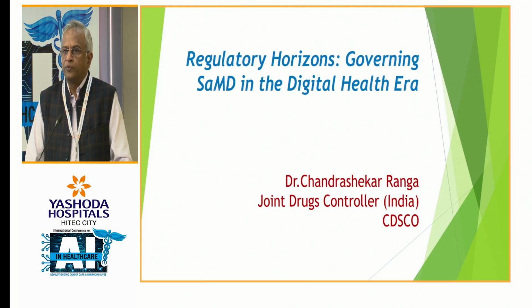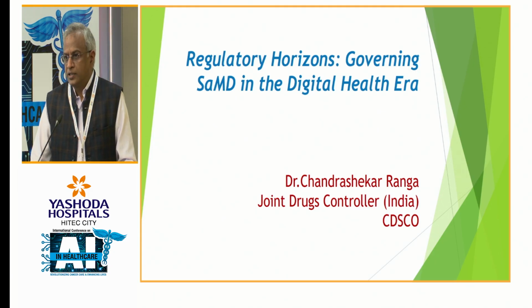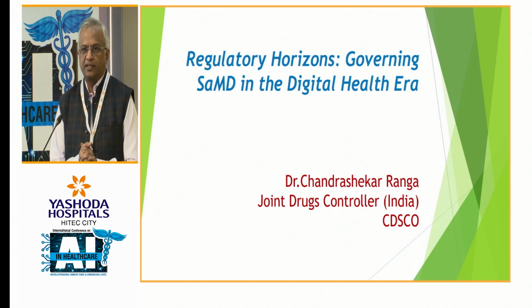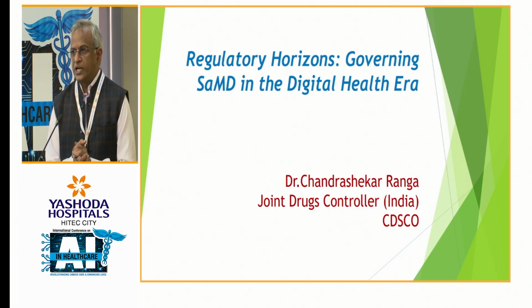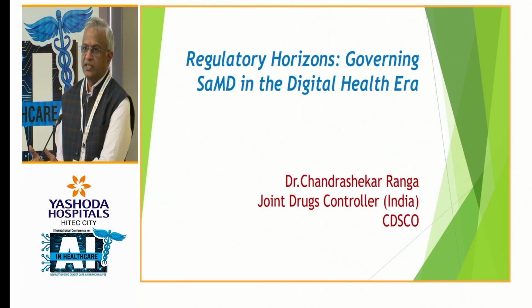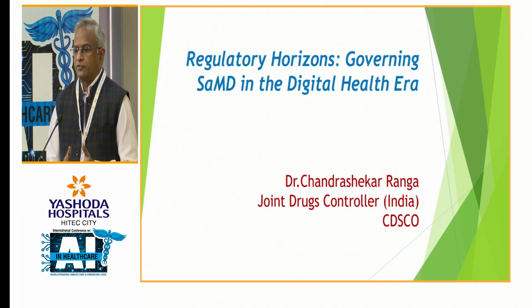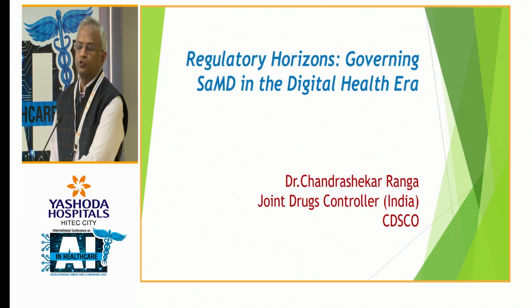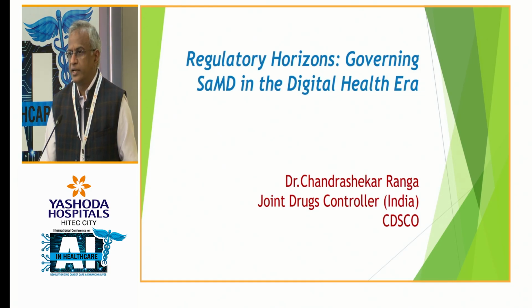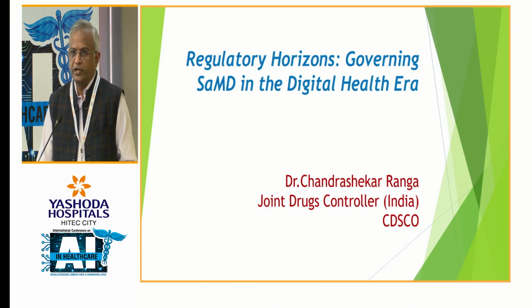So at CDSCO, what are the standards that we apply? When we regulate drugs, the requirements are different, and there we say the good manufacturing practices need to be followed for manufacture of drugs in the country. But when we started regulating medical devices, we moved away from good manufacturing practices to quality management system. The standard for the quality management system is available in ISO 13485.